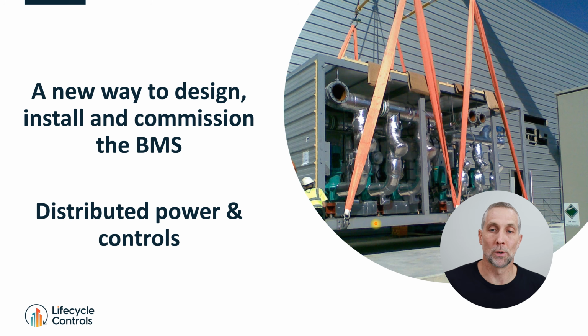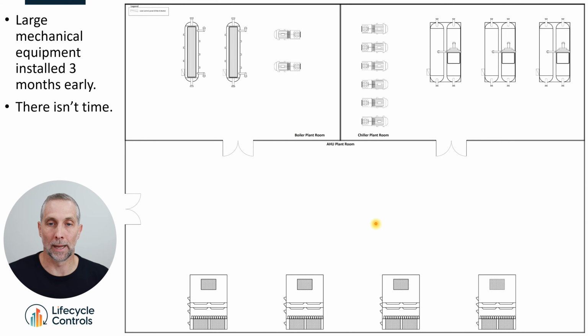So I'll be talking you through now the method that I was taught how to do this. The first thing I want to do is just start all over again at the start. Remember I said that in these big plant rooms, the mechanical equipment is installed 2 or 3 months before anything happens. You just walk past these plant rooms, that equipment just sits there doing nothing, and we're waiting for the building to progress to a point that this plant room is now ready to be worked on by mechanical, electrical, and the BMS. But we don't have time to wait. There isn't time to wait.